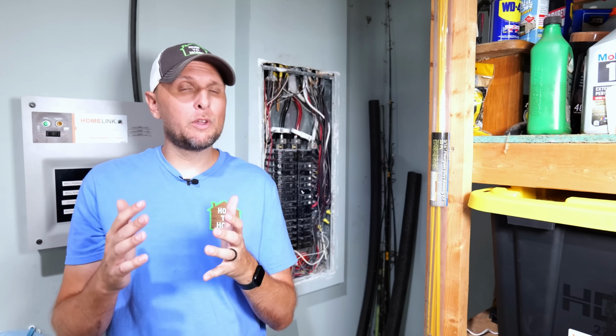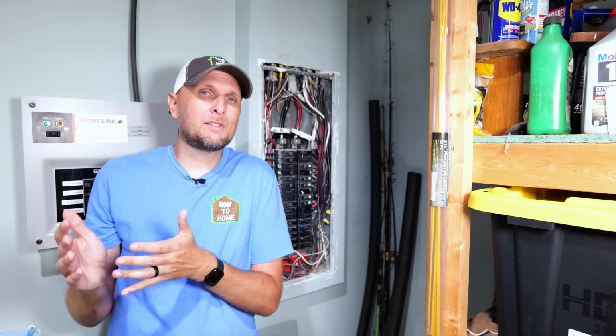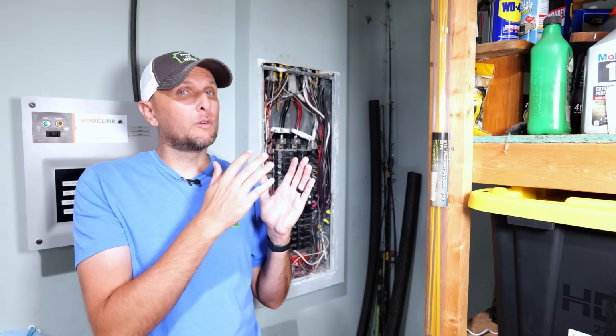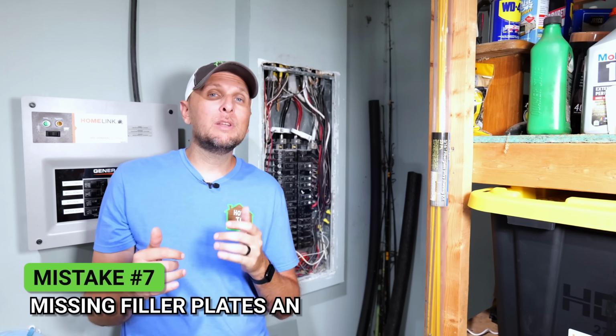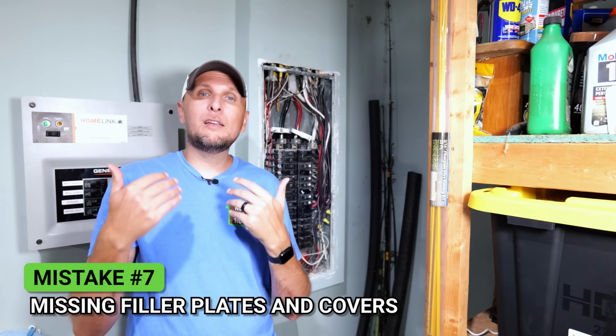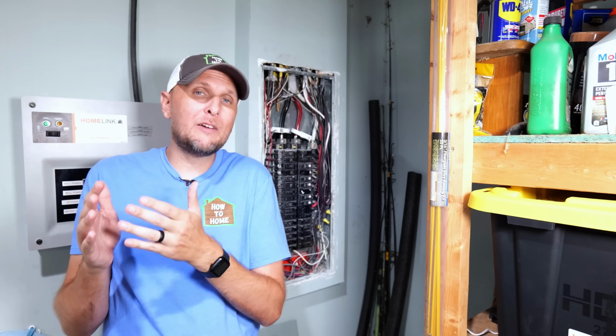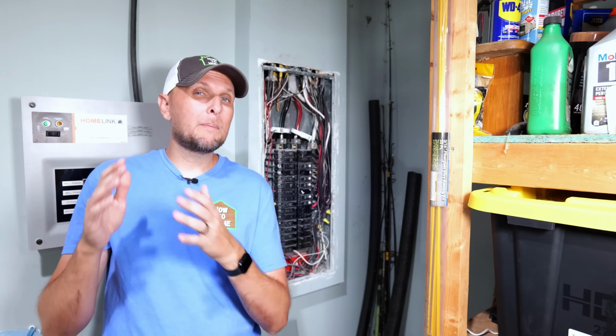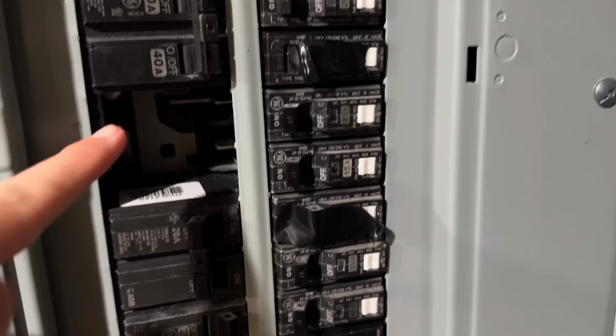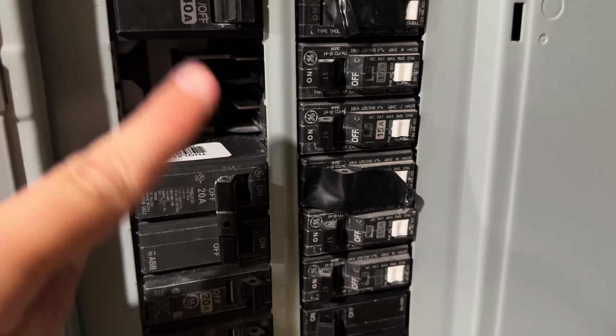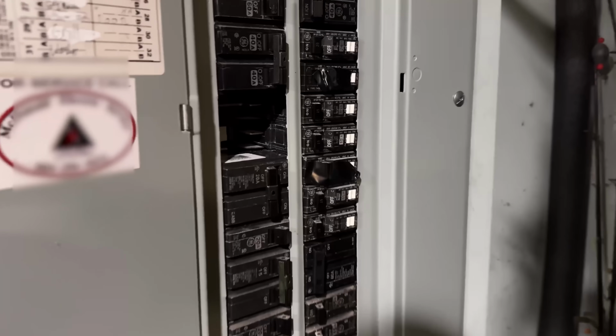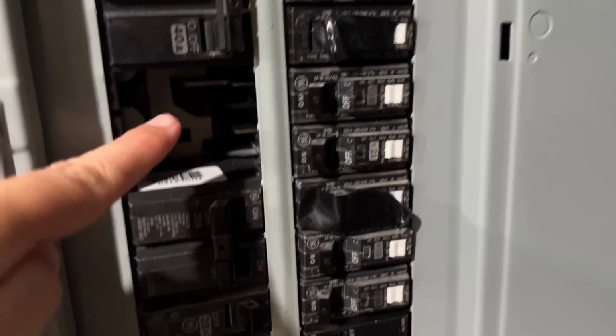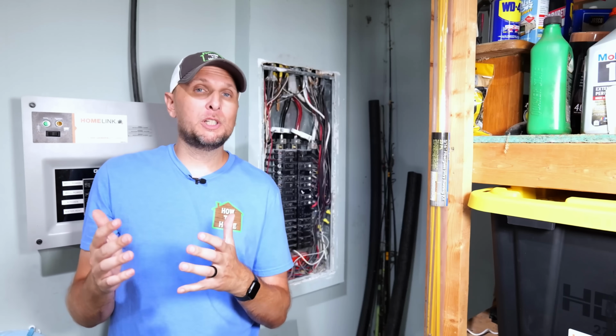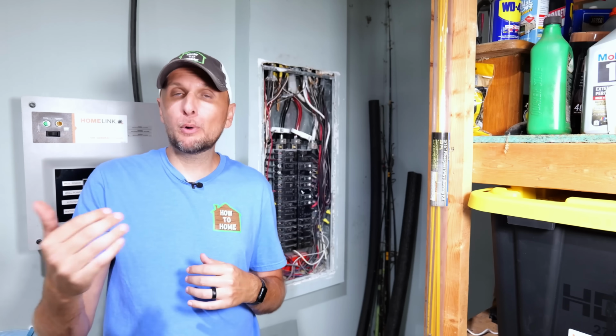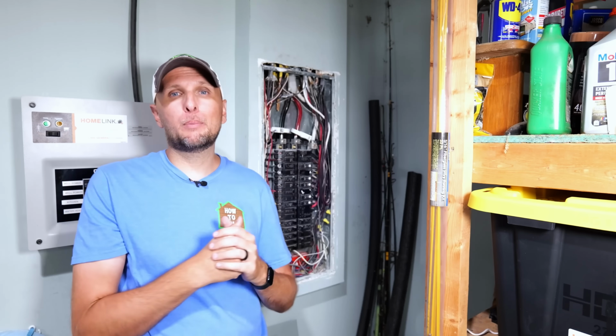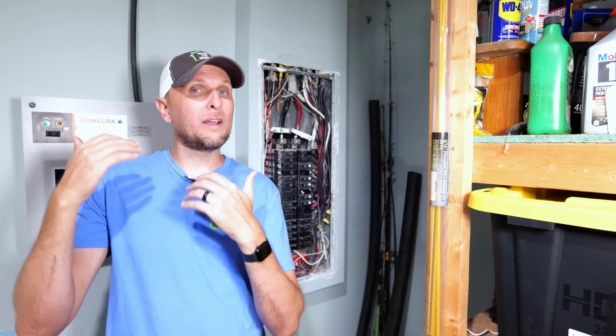This next big mistake is kind of the opposite of overloading a panel: it's leaving open knockouts or missing filler plates, which can be a giant safety hazard. Sometimes people remove a circuit breaker they don't need anymore and leave an open gap in the faceplate. Those gaps can let fingers, tools, or debris get inside the panel, risking a short or even a shock.